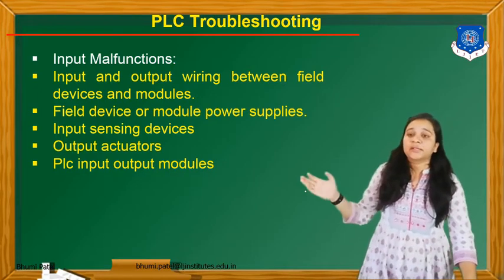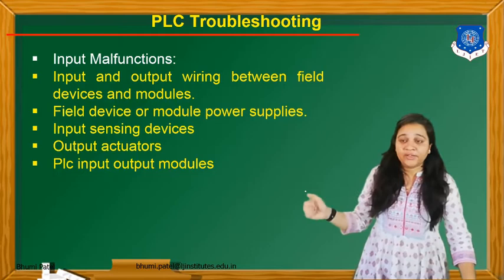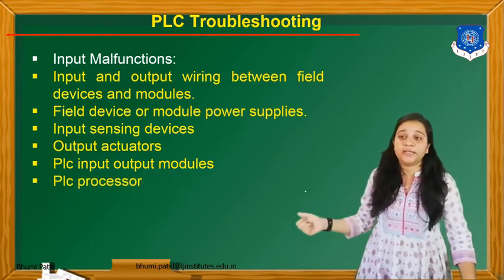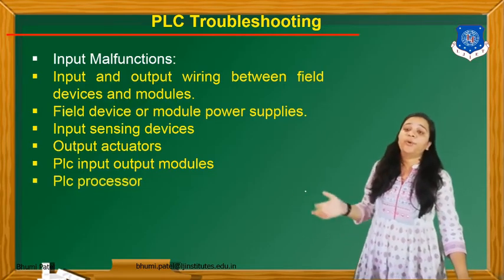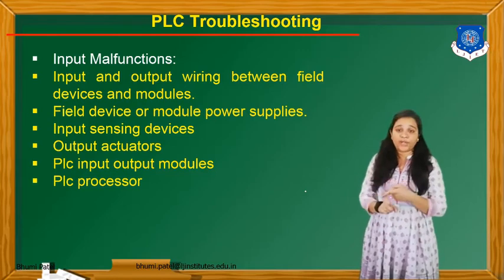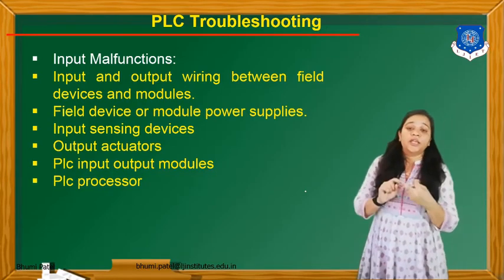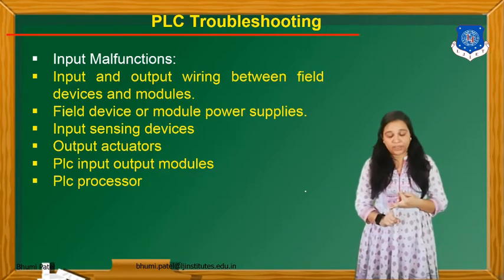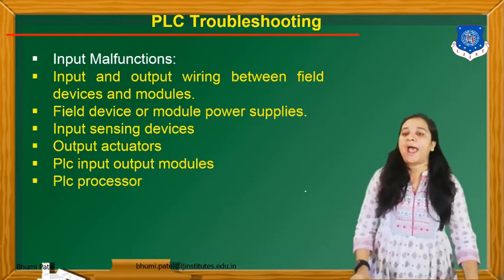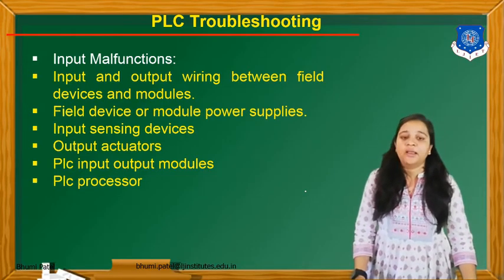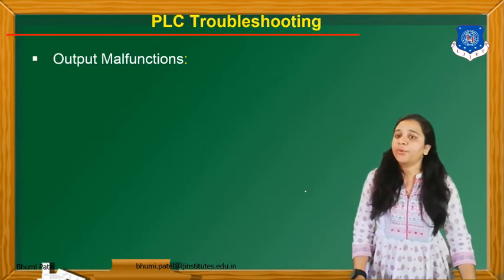So that is all for the input malfunction, and the last one is the PLC processor. So in the input malfunction, we can check the input output wiring terminals, the input sensor if we have connected it, the output actuator and the PLC processor. The next one is the output malfunctions.